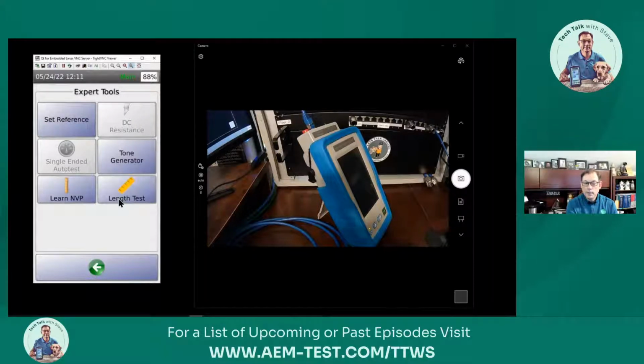The learn NVP and length test are kind of the opposite of one another. With learn NVP, if you have a known length of cable between 10 and 100 meters, you can determine the NVP value. NVP stands for nominal velocity of propagation, essentially the speed limit of the copper. This number is important for your length measurements, especially when certifying, since you need your NVP set correctly to ensure your cable isn't too long and to get accurate length measurements in your certification reports.